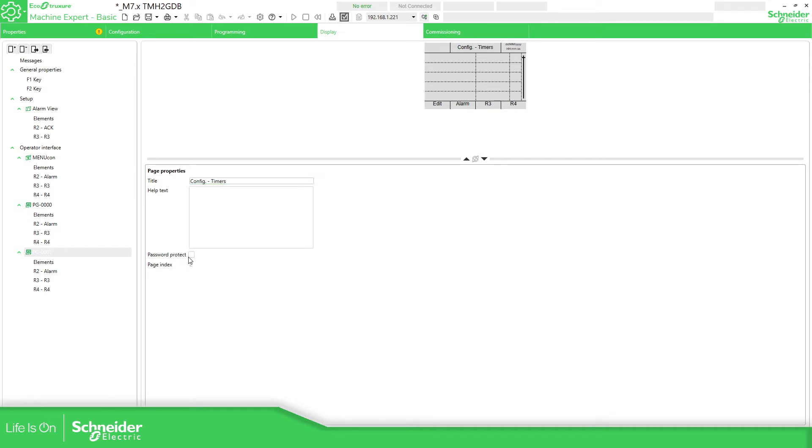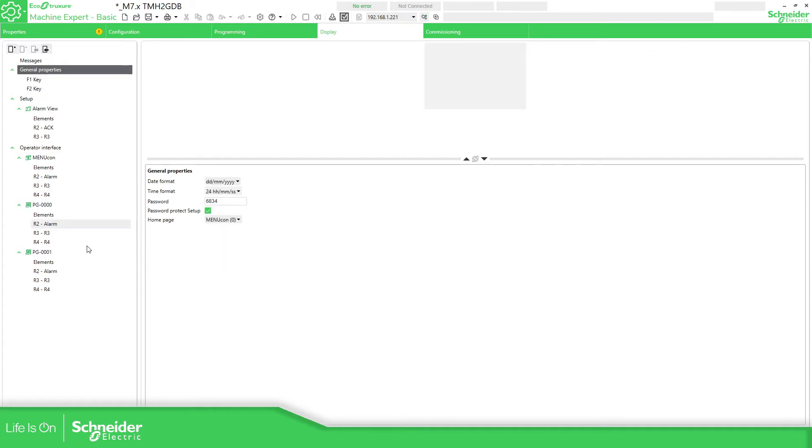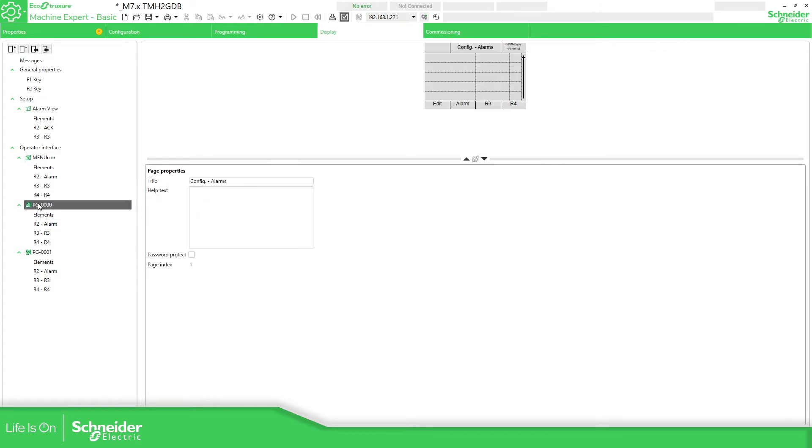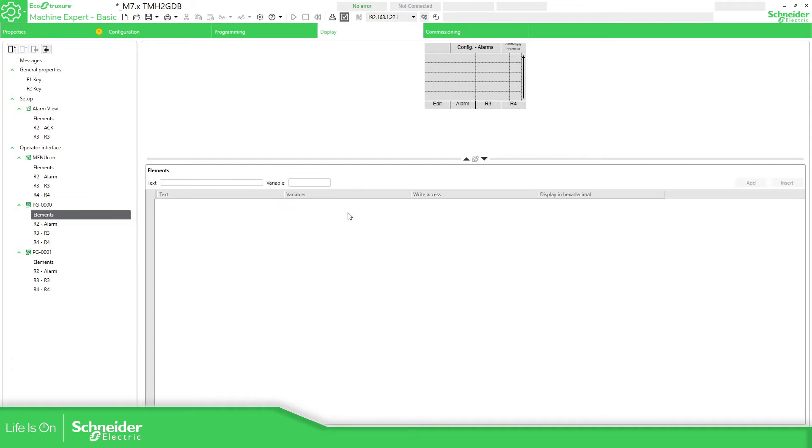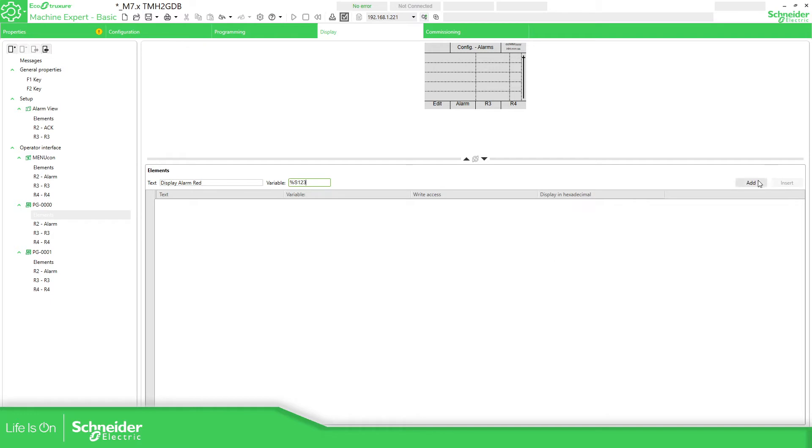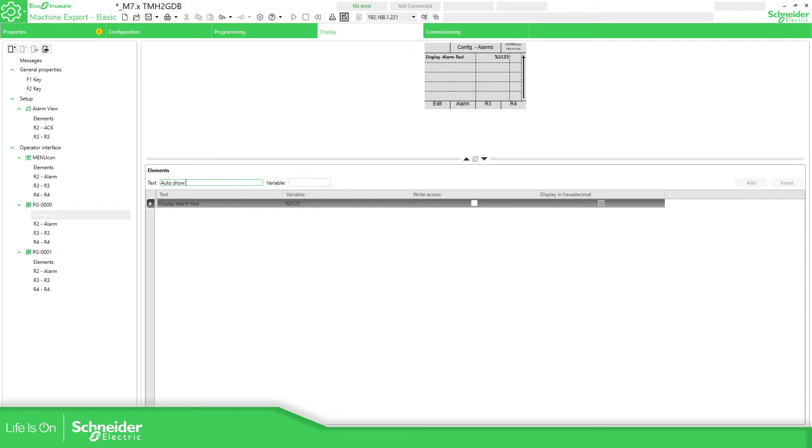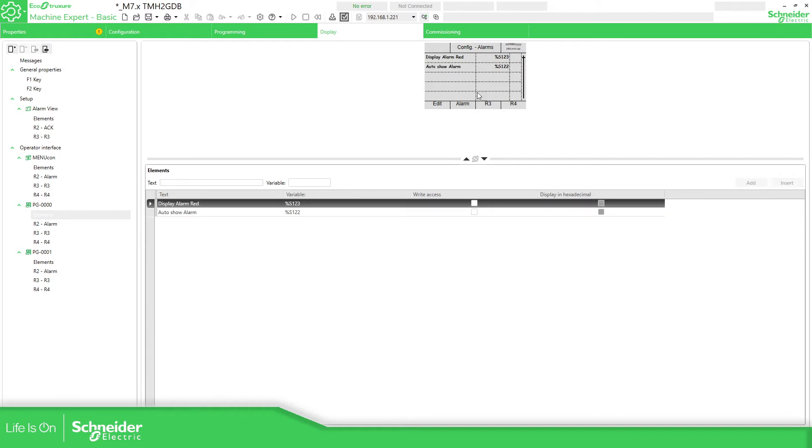You can also add the password protection in case you want it, and the password is over here, but I don't want to do that. So elements, now for the alarms I'm going to use the display alarm red, and this one is the variable %S123 that we have seen in the previous video. Auto show alarm is the variable %S122, add alarm. This is complete.